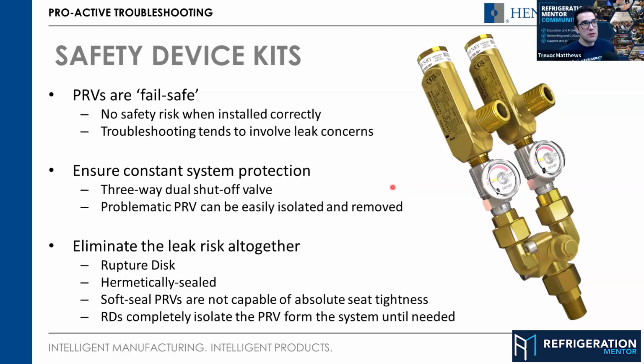Oh, that stuff is huge. So if you're in the field and it does go, and you have a leak on that one side, that should be replaced. It's very important. The big thing is looking at that rupture disc. If you're picking up a leak, go look at the rupture disc if they're on there, and it'll give you an idea you knew it leaked. Or switch it over and order a new assembly, not the full assembly, but just the rupture disc and the spring. Get the same ones. You don't want to oversize or undersize them. Get the exact same ones, order those up, and protect your customer, because this protects everybody and that system.